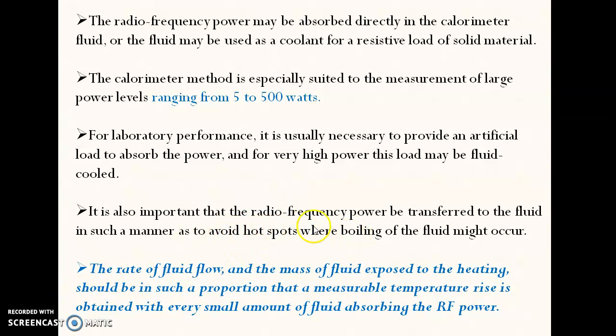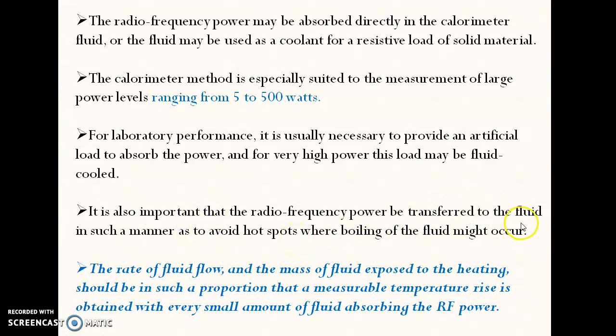It is very important that the radio frequency power being transferred to the fluid should be transferred properly and should not generate any hot spots, because if at a particular point of the fluid flow the temperature rises beyond a certain range, then obviously the fluid will start to boil. So it is important that there should not be any hot spots generated due to the absorption of power in the fluid. The rate of fluid flow and the mass of fluid exposed to the heating should be in such a proportion that a measurable temperature rise is obtained with a small amount of fluid absorbing the RF power.